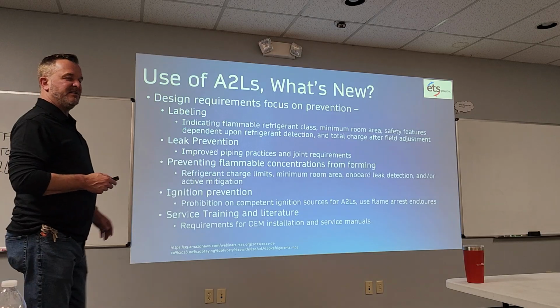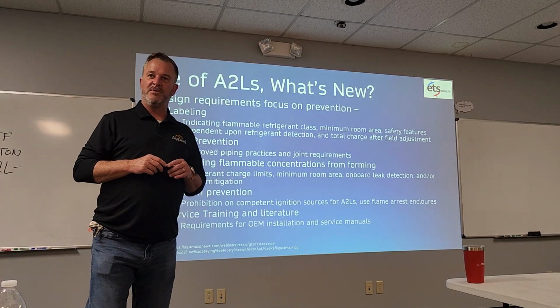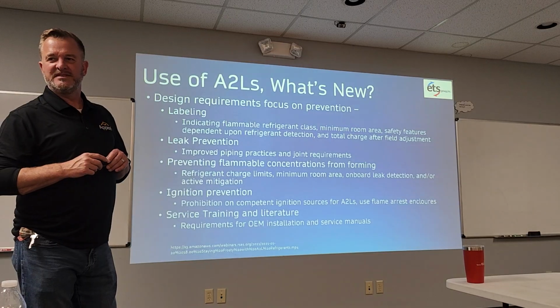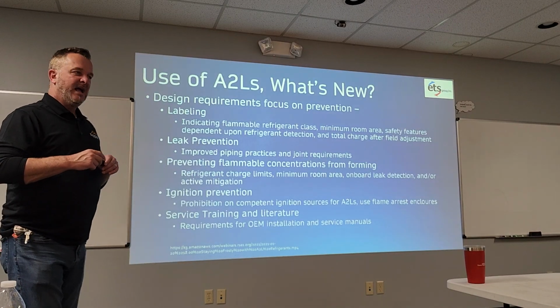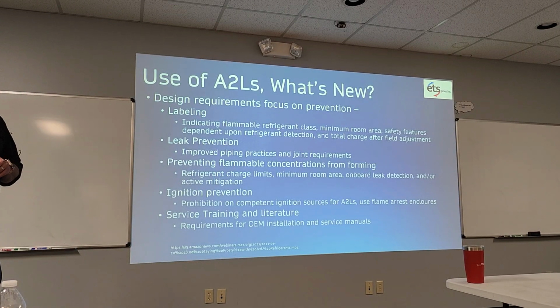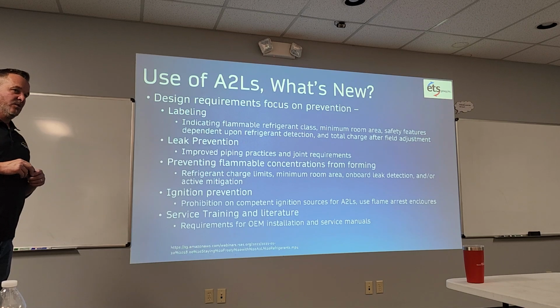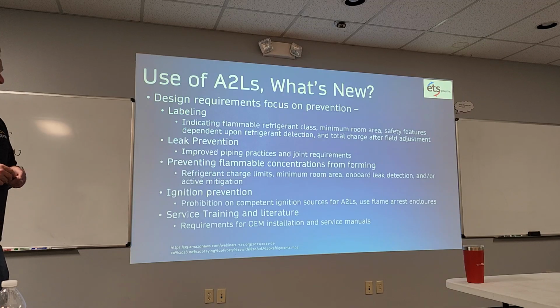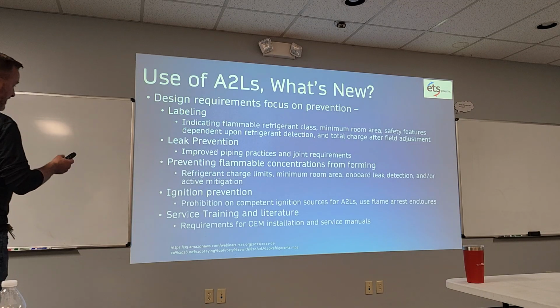And I think that was one of the main reasons, you guys remember when they were doing 410A systems, they put that AC Renew stuff in, because TXVs were getting all clogged up? The acids. I think that happened for two reasons. One was the brazing practices, you left all the debris in there. And two was the POE oil and not getting vacuum, not getting the moisture out of there. I think those are the two main things that caused those TXV issues. Preventing flammable concentrations from forming, obviously.